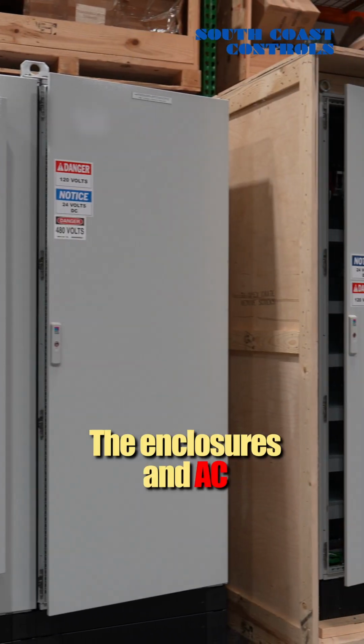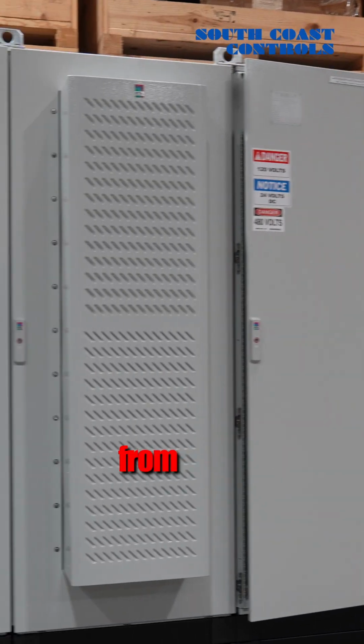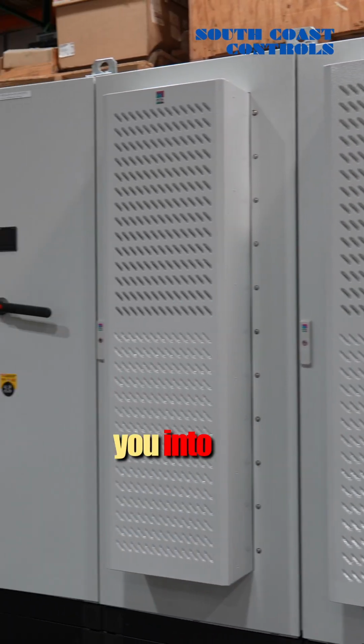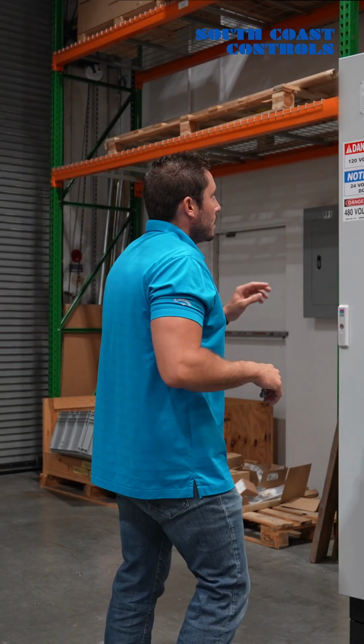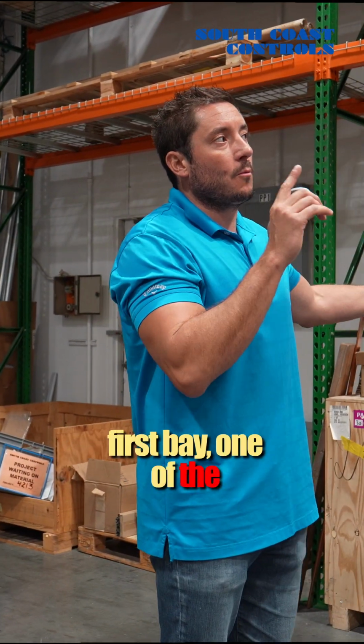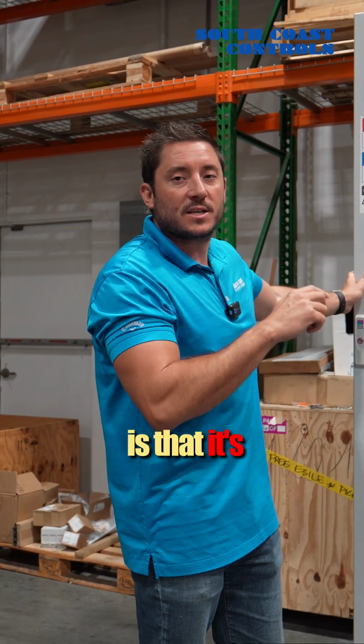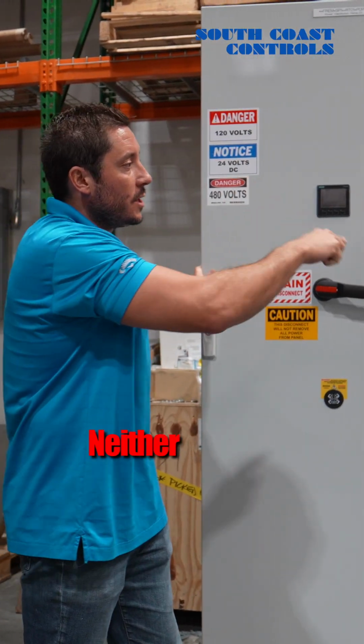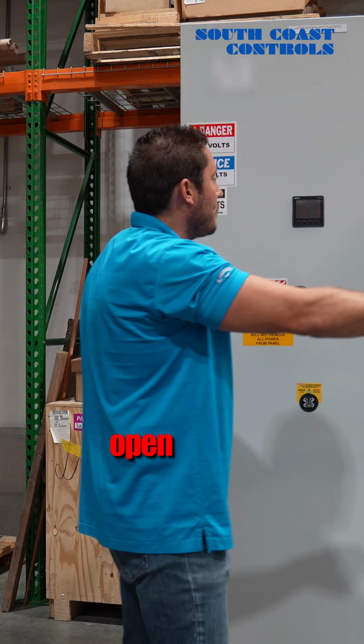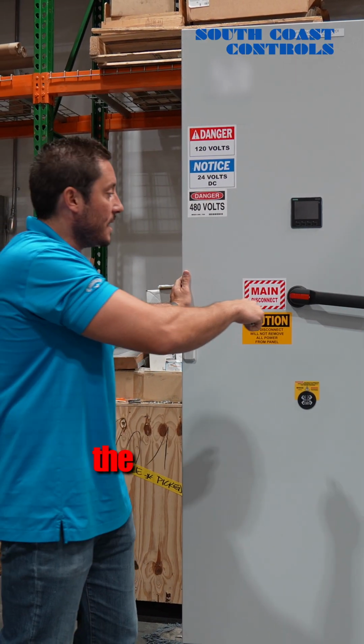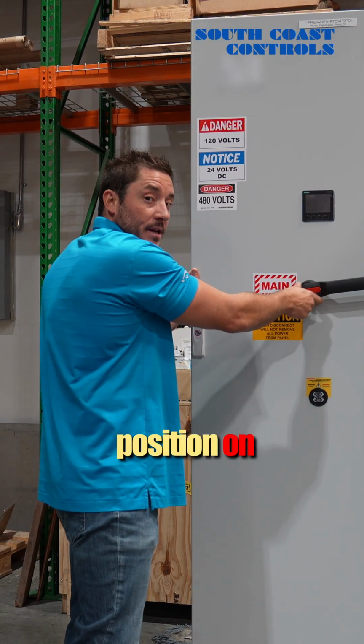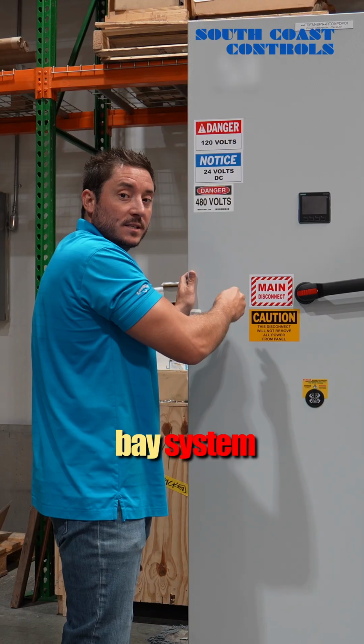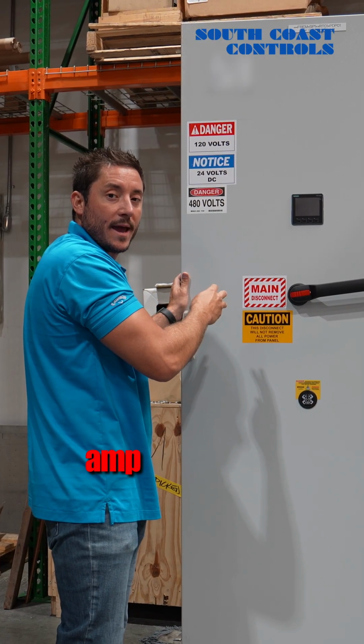The enclosures and AC units you see are all from Rittal. Now I'm going to take you into the first bay. Before we open up the first bay, one of the more unique things about the 6-bay system is that it's all mechanically interlocked.